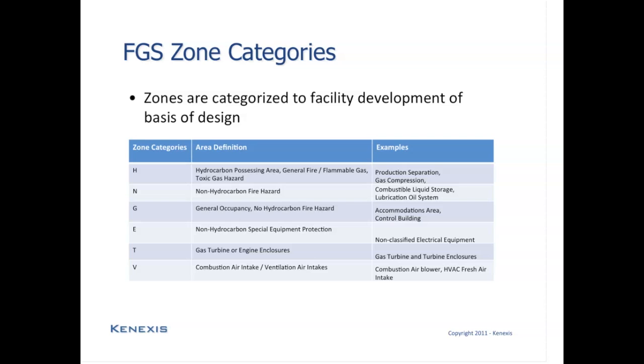E, the next type of zone, is non-hydrocarbon special equipment protection. And typically what we're talking about with a type E zone is a zone where we are concerned about separation of a hydrocarbon area from a non-hydrocarbon area, specifically because the zone contains unrated electrical equipment. So this would include things like motor control centers or instrumentation and control rack rooms, where if hydrocarbon were to ingress into that area, it could find a source of ignition and cause an explosion.